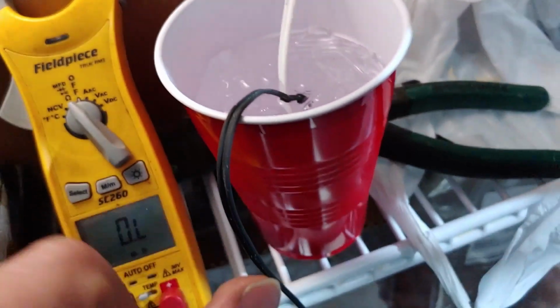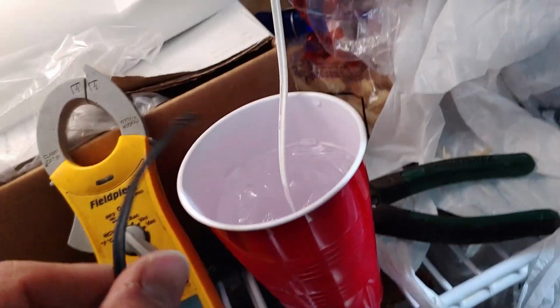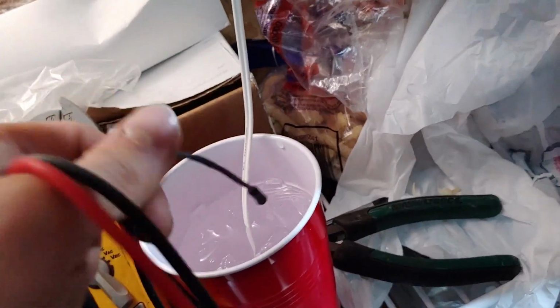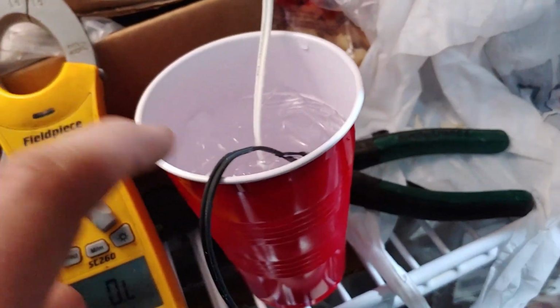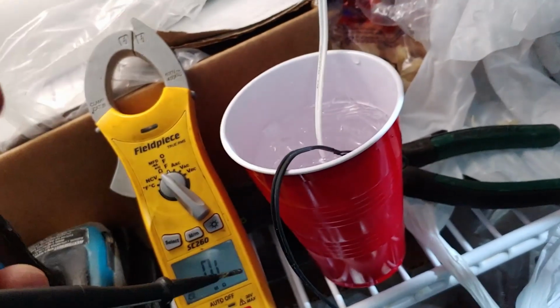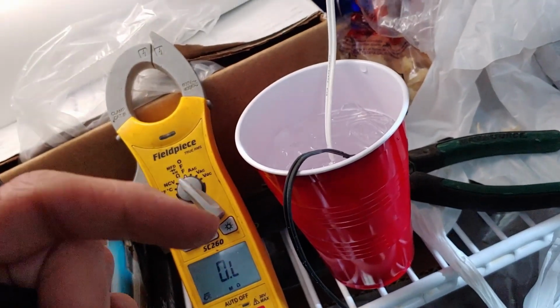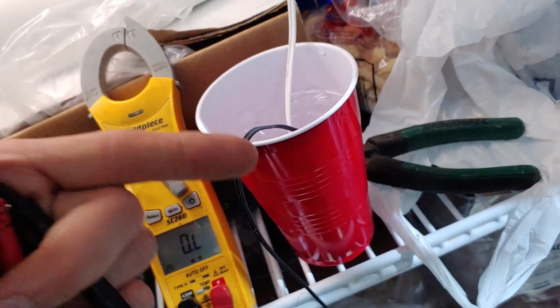And you can see I have a cup of ice water here. This is the new probe that I had as a spare at this location, and we're testing it against the old probe. They want you to test it in a glass of ice water like this because that's guaranteed to be 32 degrees, and the ohm rating changes depending on the temperature. So we're going to check the ohm rating on that one first.